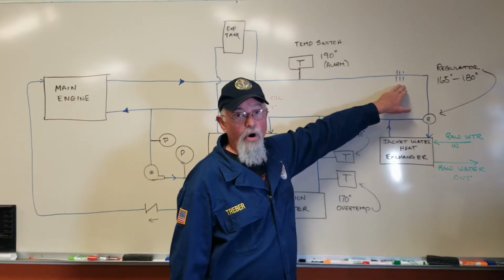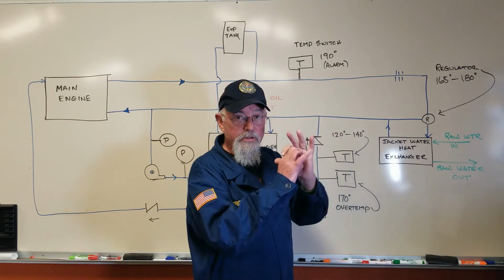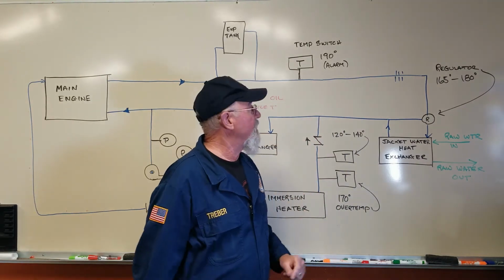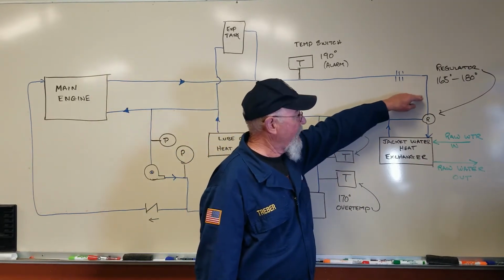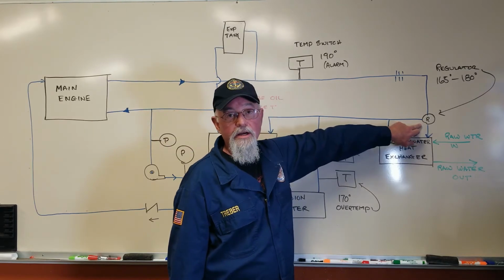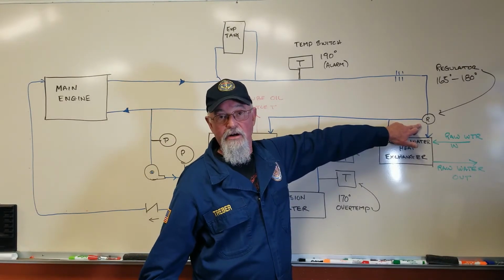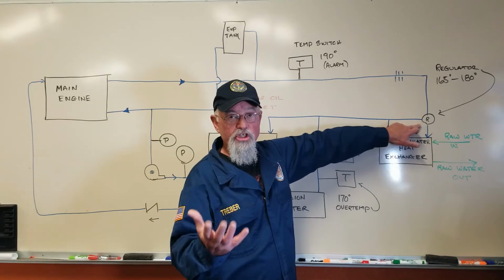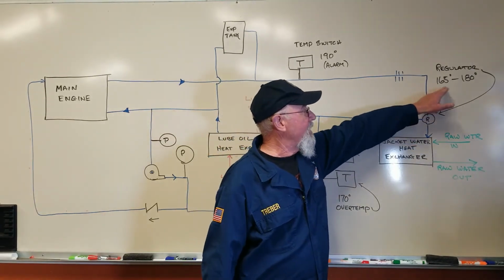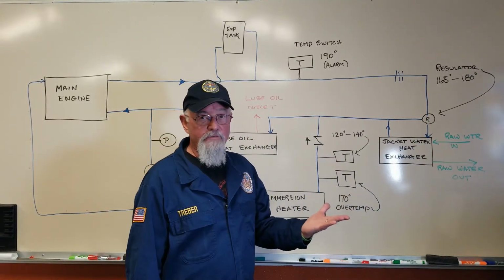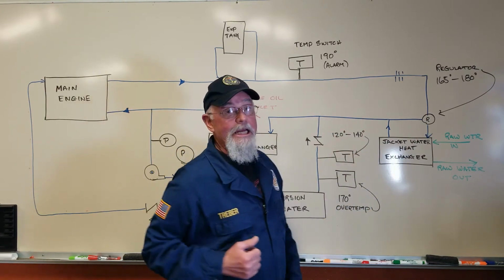Downstream of that, we've got an orifice that restricts the flow, so it's smaller than the inside diameter of the jacket water piping. And then that jacket water comes down to this guy right here, which is a regulator. So it's also a temperature sensing device. And you see I have the temperature written up here, 165 degrees or 180 degrees.